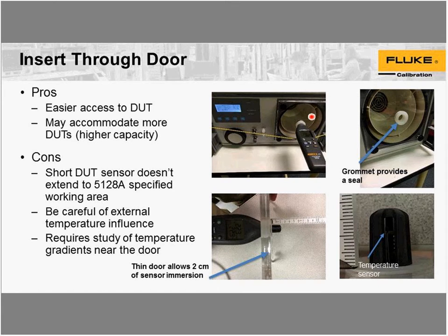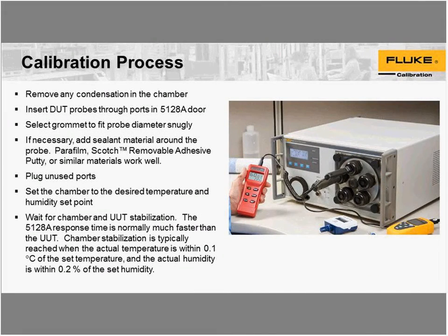For the sake of time, I'll quickly go through this. This is basically a general procedure for measuring humidity, talking about installing a sensor, making sure that it's sealed, and then working your way through the temperature and humidity points.